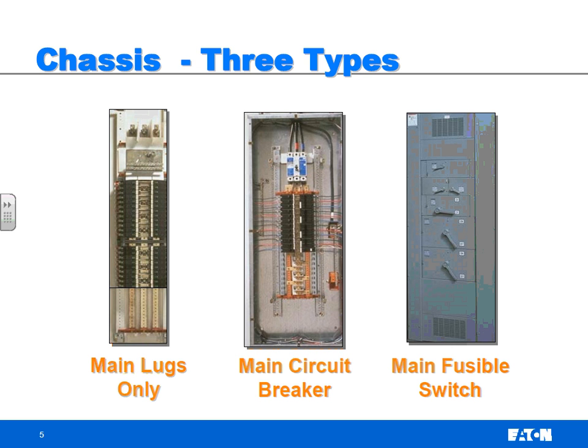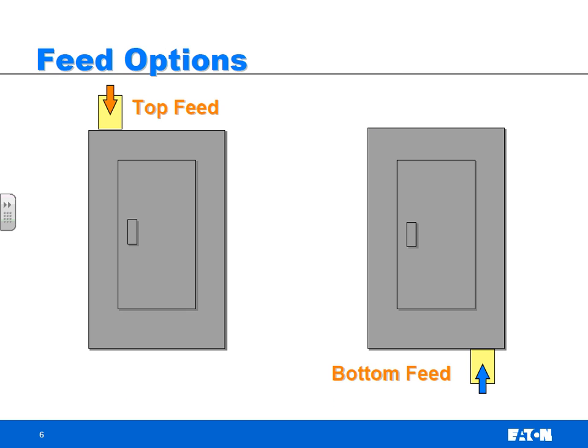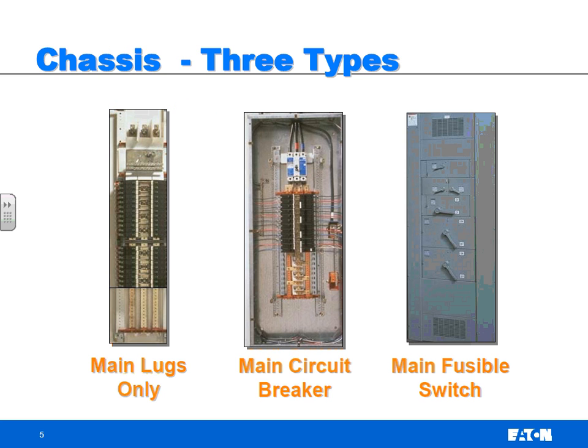In motor control centers, as we're talking about these, they have something called an HMCP, which is similar to a molded case switch. It's got the magnetic protection in there, but not thermal protection. And they use that in conjunction with overload relays that are specifically set for the motor. So those are kind of the three different methods of circuit breakers. Oh, and the last one on here was the main fusible switch.